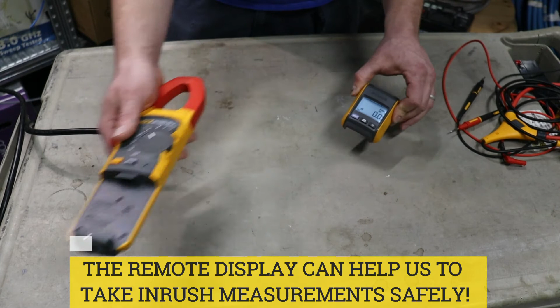So a good example of when you would use the inrush and the remote display would be if you're in a piece of equipment where you need to put the meter and the leads inside and close it, like a disconnect for example, or a motor starter. You can throw that in there, close it up so you're safe, and then energize it with your remote display over where it's safe, so you can safely document the readings. While this is over where the live voltage is all taking place.